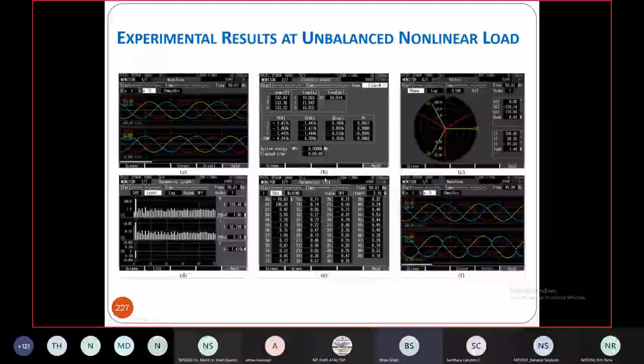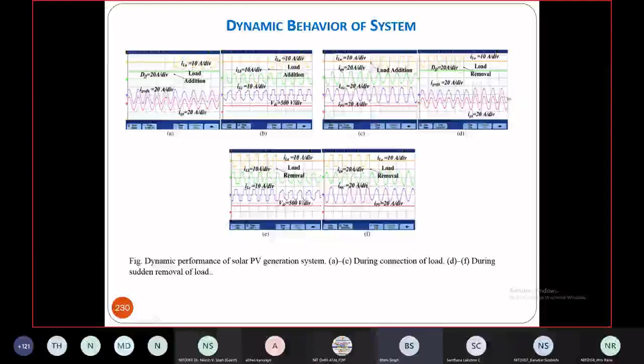And this is the typical case when your load is suddenly put on, and how the control takes care of this. The grid currents are not affected, the grid current remains quite intact under solar variation and also load variation, where one phase load is varied. Only the magnitude of the grid current will increase, because if one phase load is removed, the power consumed by the load, a line to line one phase load, is reduced, so more power will be fed to the grid, because solar generation is fixed. And that is how the system is working with solar generation without much problem.